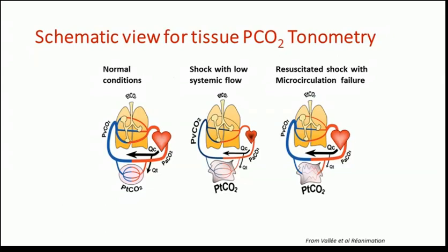And we added a second patent on that to perform a vascular test. We warm this transducer. Normally, when you warm a vessel, you dilate. If you dilate, you flow more. If you flow more, you reduce the CO2, which is no longer stagnant, and the gradient goes down. If the gradient is not changed by the warming, you have a vascular problem. Thank you very much.